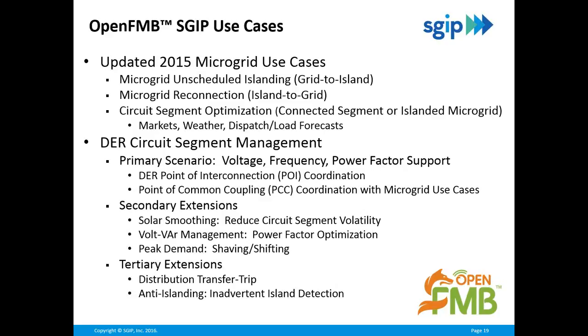And last but not least, these tertiary extensions. These are really use cases that serve as a safety net, just in case—when you're starting to have a high penetration of solar and a lot of bidirectional power flow, your existing protection schemes, which were designed for a one-way power system, are not desensitized by the high penetration of DER.